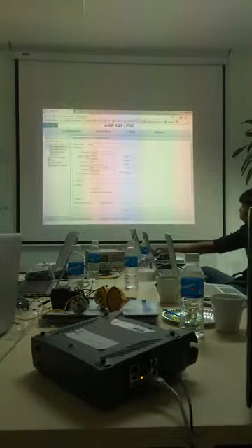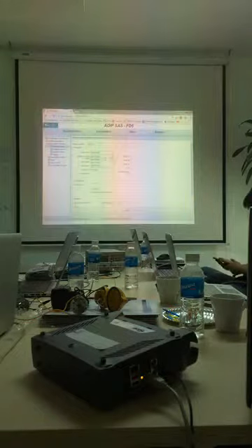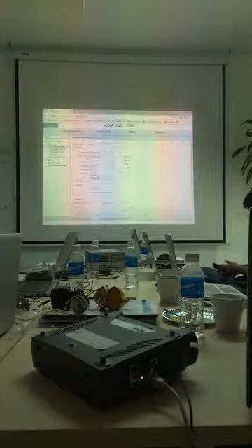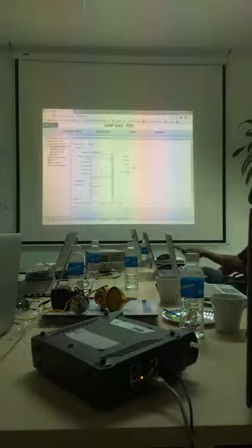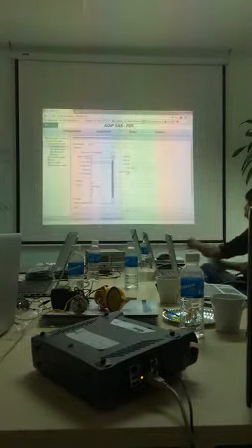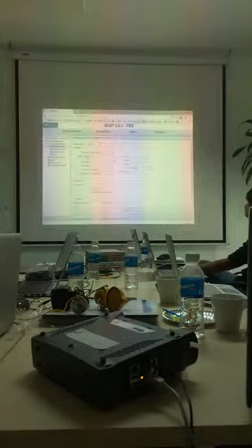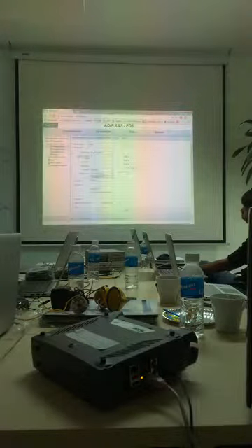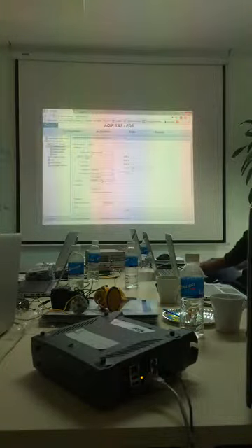Then resistance, same. You can select range, and resistance can be plugged in different ways, 2, 3, 4 wire. So we have thermocouples. You can put the type of thermocouple because all of them have different results. Accuracy, and then thermocouple, you can show the result either in temperature or voltage, because the result of a thermocouple is millivolts. So there you select what you want to see.